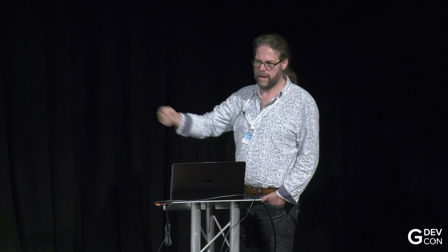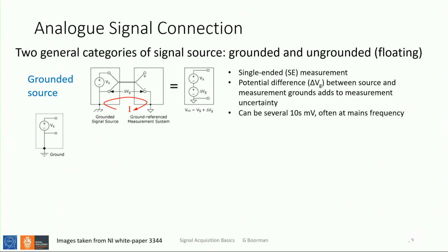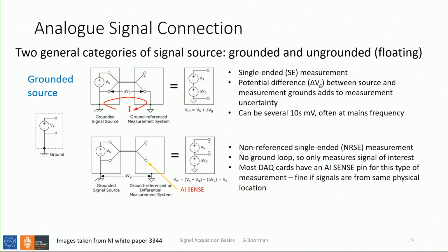So this is okay if you've got a system that's generating your signal and measuring it probably in the same rack or the same chassis. You don't generally have a problem. When your signal is coming from the room next door, or the rack over in the corner of the room, this is when you start to find the ground loops actually occurring. So how do you get around this? Most of these ADCs have a pin called AI sense, or analog input sense. This is like an alternative reference to ground.